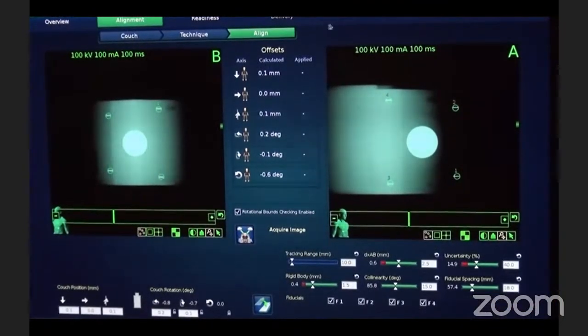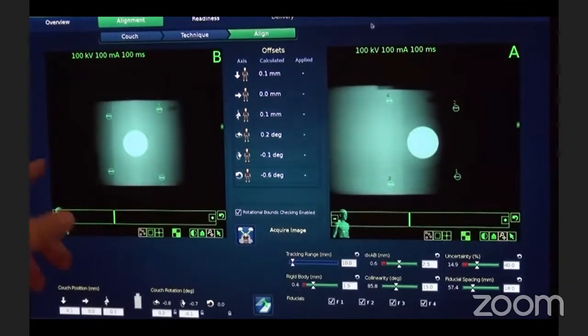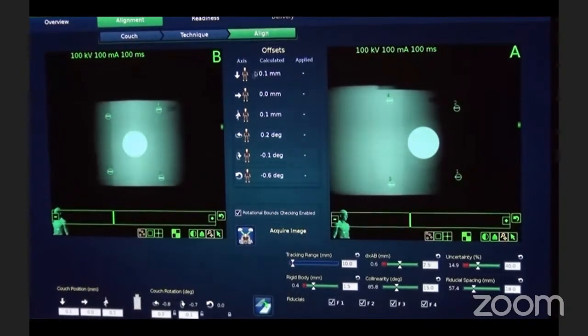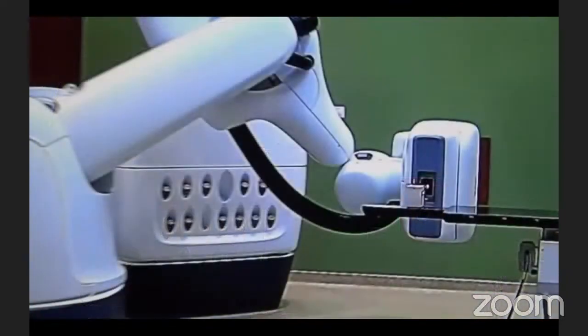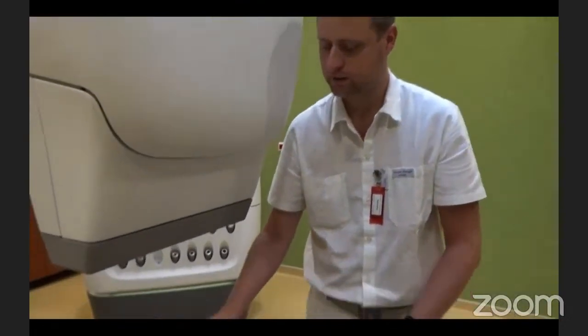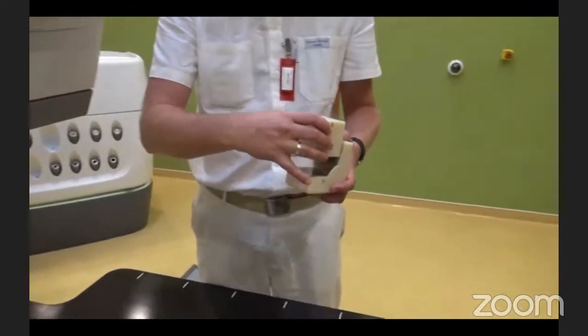First, we verify the AQA phantom position on the couch with the help of the 4 gold markers with the fiducials, and if the tracking is precise, we deliver the 2 beams on the phantom, the anterior and the lateral beams. After delivery of the AQA test, we will get this result.